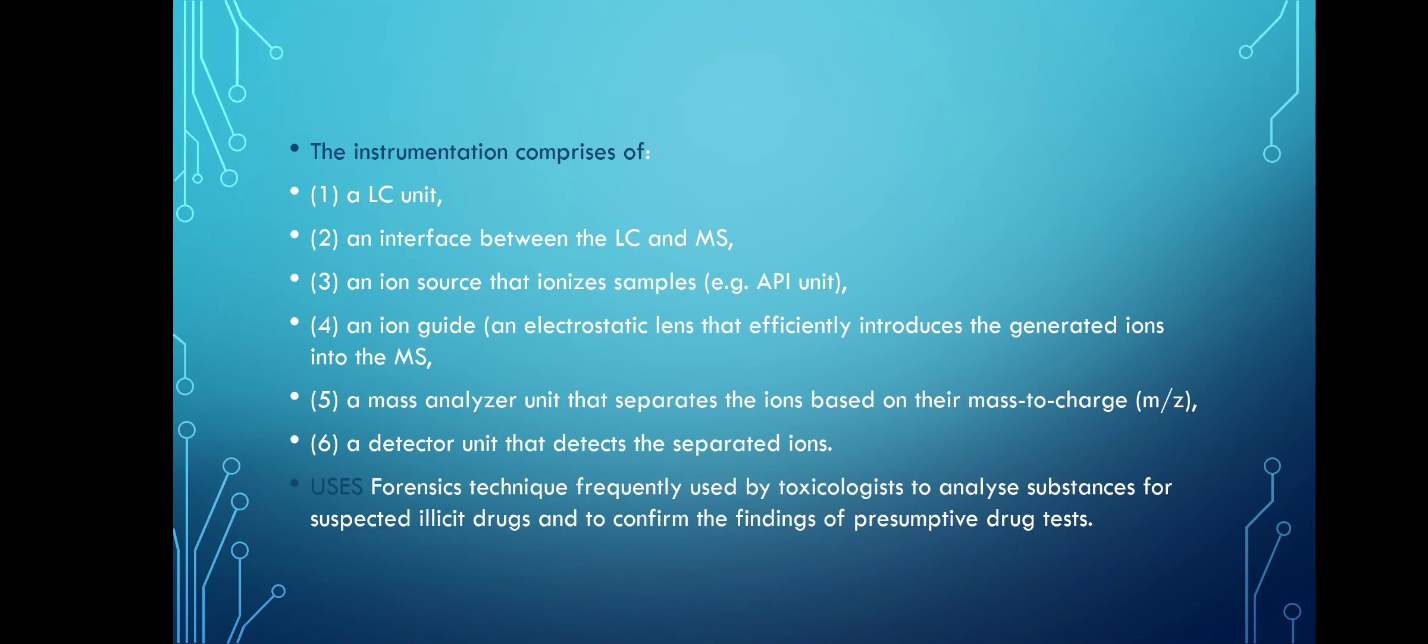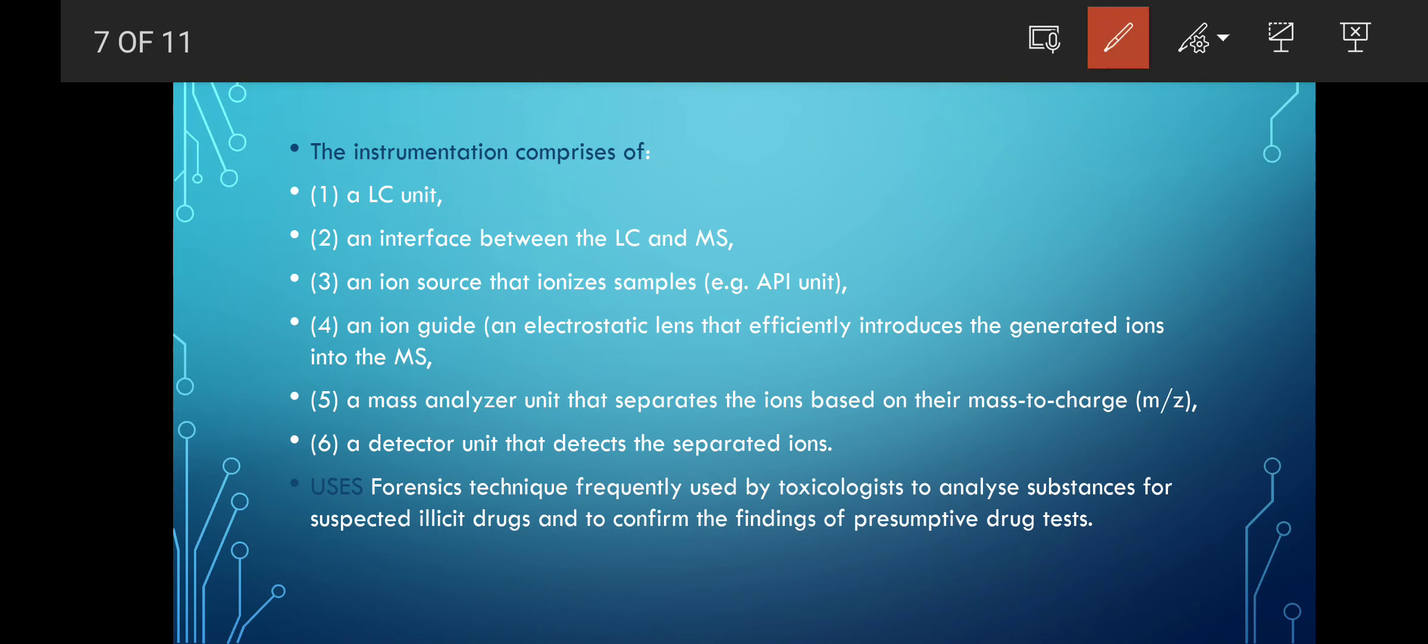The instrumentation comprises the LC unit, the interface between LC and MS, the ion source that ionizes the sample like the API unit, the ion guide, an electrostatic lens that introduces the generated ions into the MS. A mass analyzer separates the ions based on mass to charge ratio, and the detector detects the separated ions.